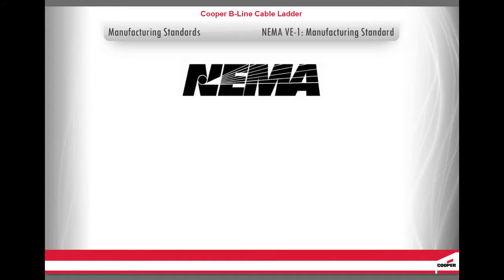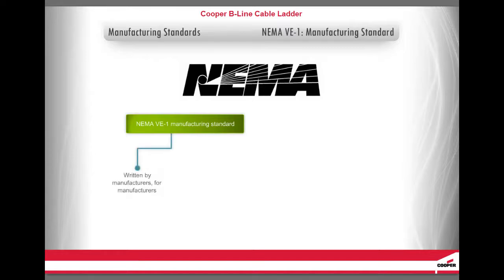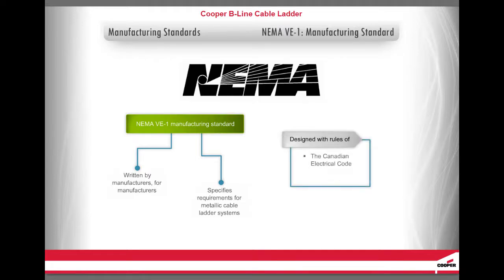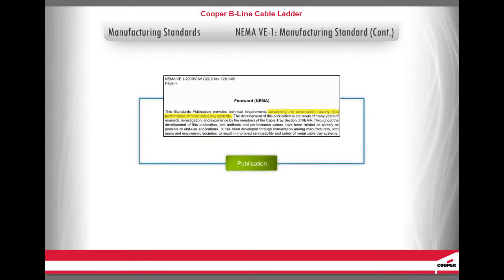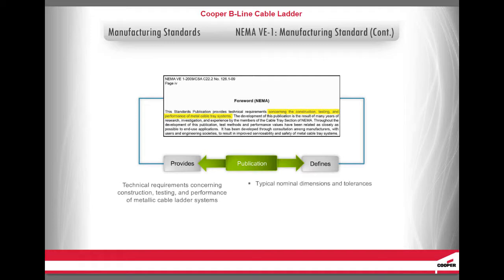Let's look at the NEMA VE-1 Manufacturing Standard. The NEMA VE-1 Manufacturing Standard was written by manufacturers for manufacturers. It specifies the requirements for metallic cable ladder systems designed for use in accordance with the rules of the Canadian Electrical Code and the National Electrical Code. The publication provides technical requirements concerning the construction, testing, and performance of metallic cable ladder systems. It defines typical nominal dimensions and tolerances, testing methods for load and electrical continuity, material definitions by the American Society for Testing and Materials, and labeling requirements.